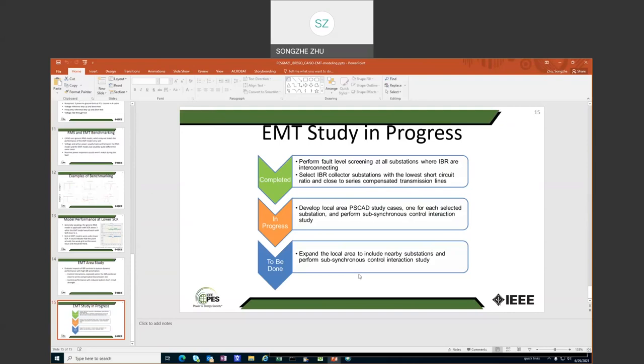For us, one collector has several thousand IBRs connecting to it, and there are 10 to 20 different plants. So collecting models for just one location in order to perform the study, we need models from all those 10 to 20 generator owners, and we need to validate them and make sure they are good enough to perform the study. Once we have the models, we can run the local area study, then the final step will be to expand the local area. We start with one substation, then we will expand the local area to include the nearby substations, and then perform SSCI study.